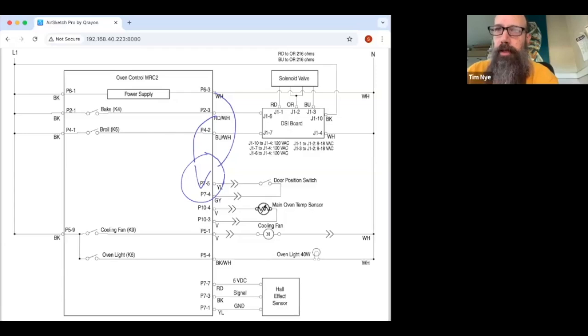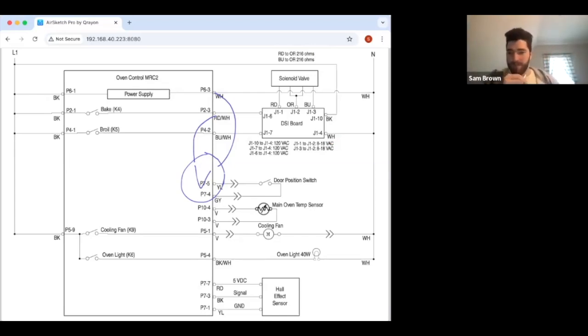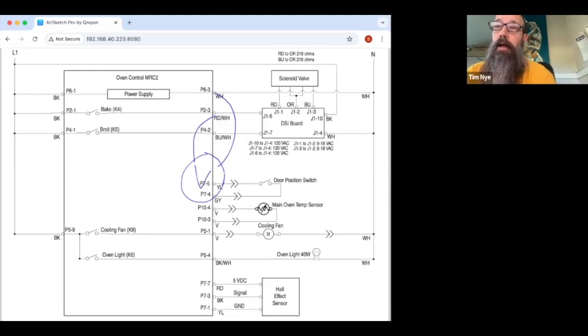Right here, if you look up top, it'll show you the ohms of the solenoid coils themselves. And in the tech literature, it'll tell you that if either one of them is bad, neither of them will work. Correct, it does say that. Even if you had a broil, I've been on this before, where my tech was struggling on the call, and it ended up being the broil solenoid was cracked on the gas valve. As it would heat up, it would swell and then shut the flame off. It ended up being a cracked coil on that solenoid of the broil. Interesting.